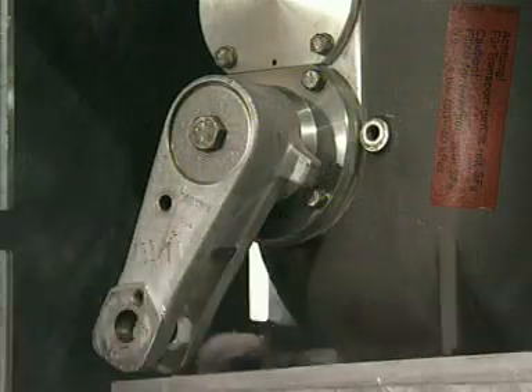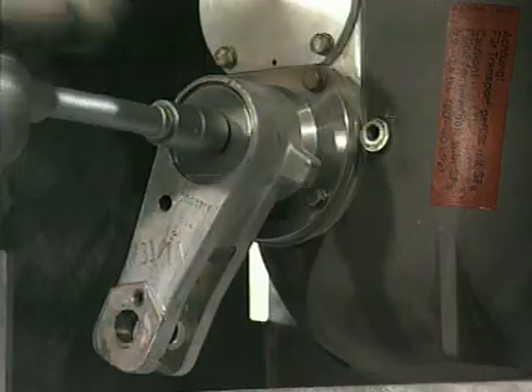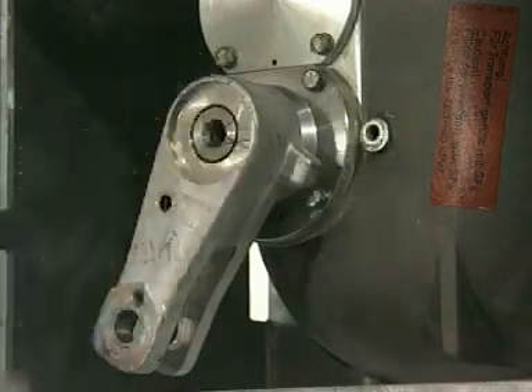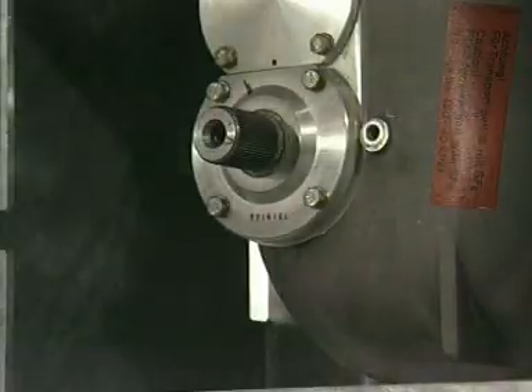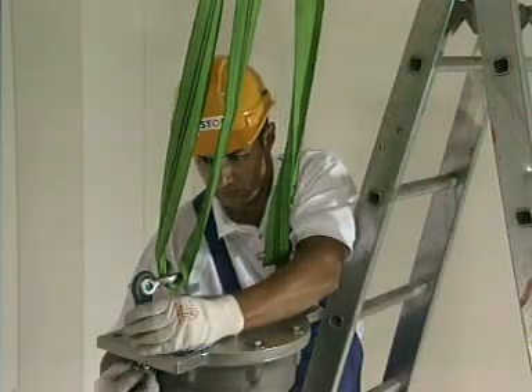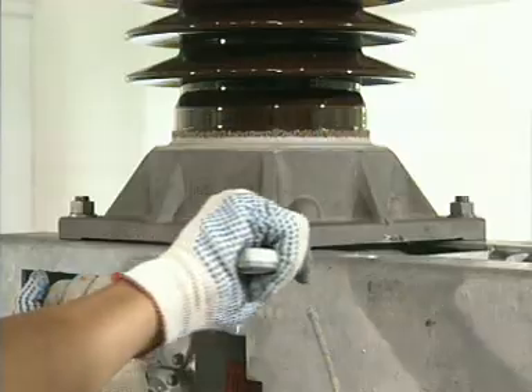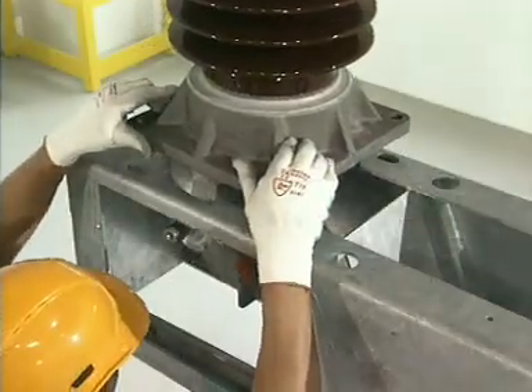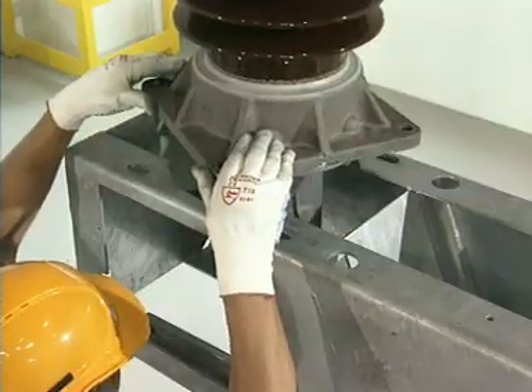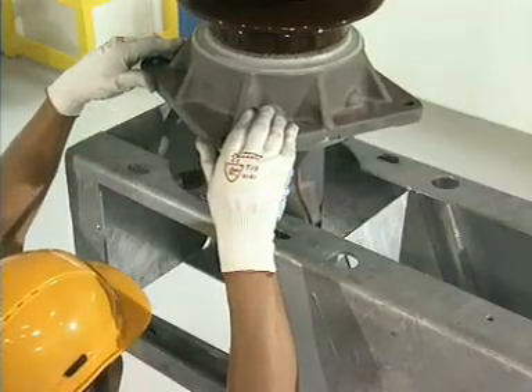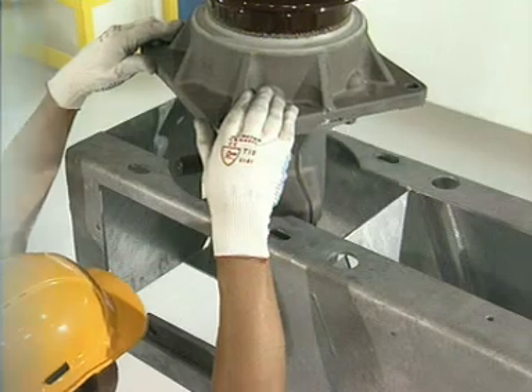Detach and remove the connecting rod from the pole column lever. Loosen the bolt on the lever and remove the lever from the torque shaft. Attach the pole column to a hoisting rope and remove the bolts on the pole column flange. Rotate the pole column approximately 30 degrees from its installation position and lift it out of the base frame.